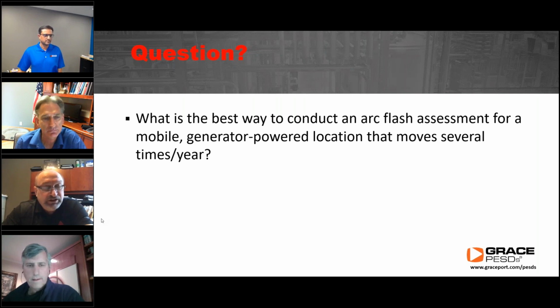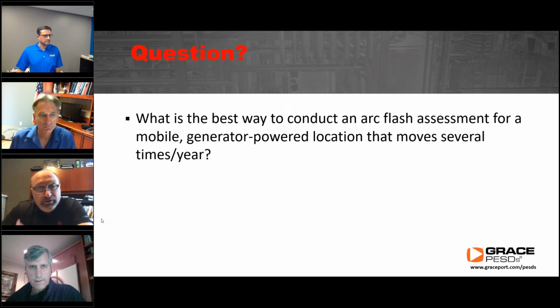So again, you've got two choices: incident energy analysis, with some challenges because of potentially the cable lengths to sub-distribution, as long as the generator doesn't change, right? I'm just trying to answer this one with an understanding that it would be temporary power for construction, probably, with the power distributed off the panelboards for portable cord and plug connected electrical equipment, lighting, and anything else that's fed off of this generator. So I'll open up to Charlie and John maybe to offer some comments as well here.